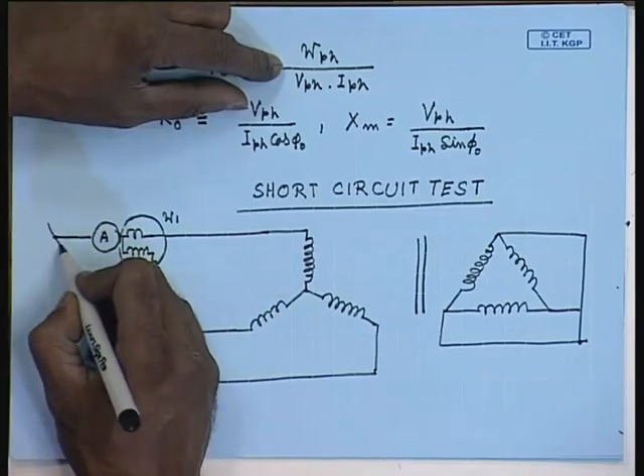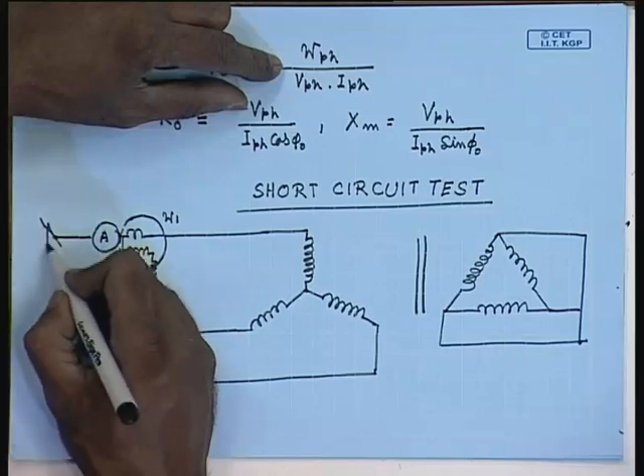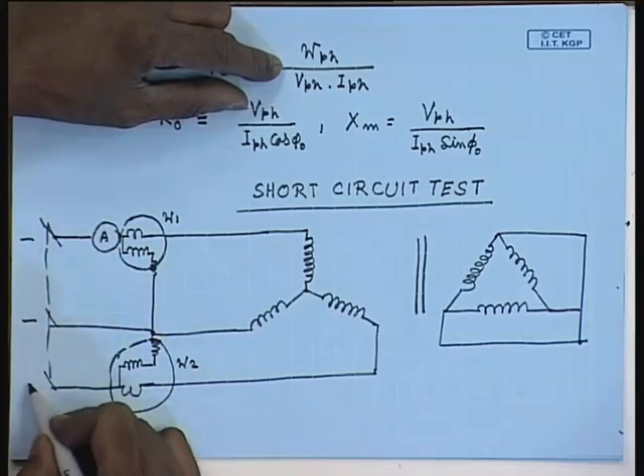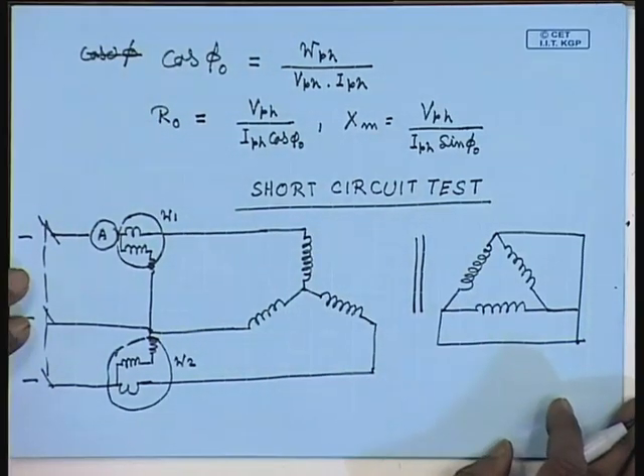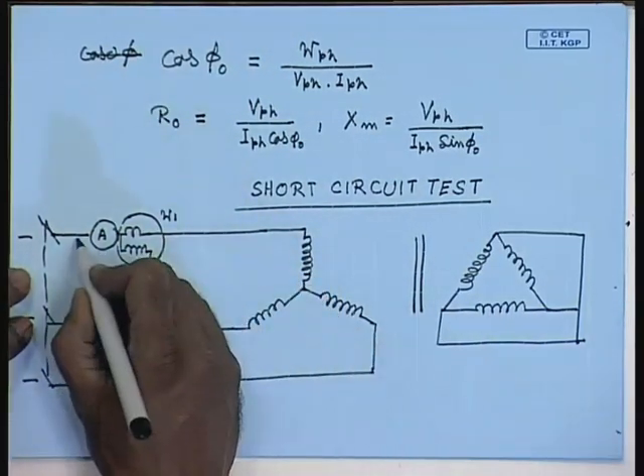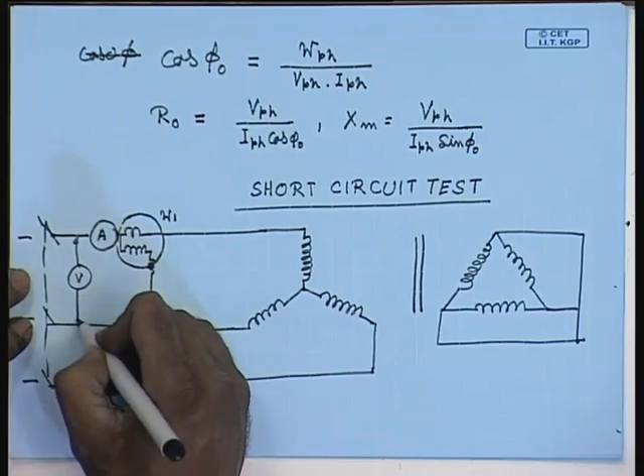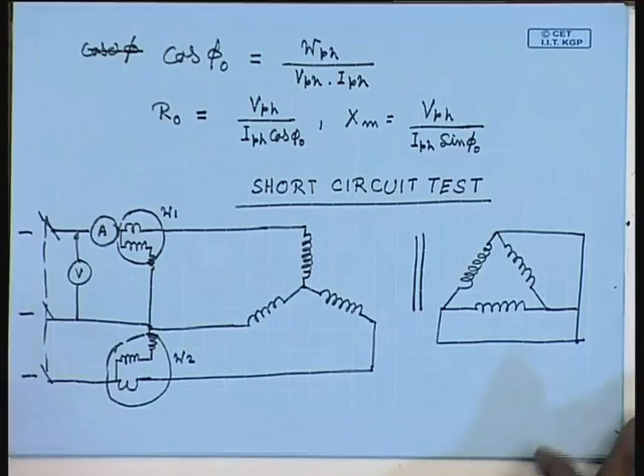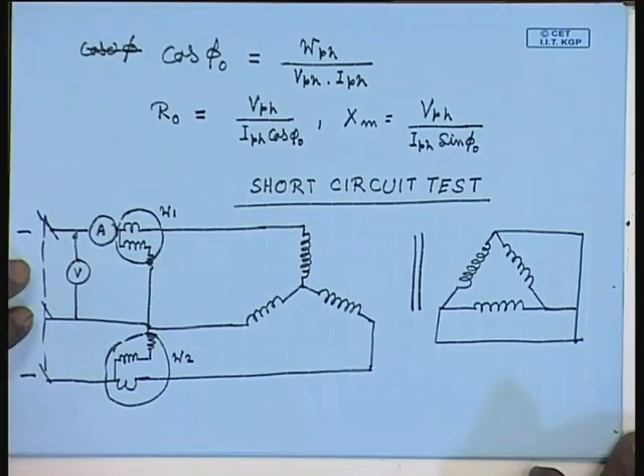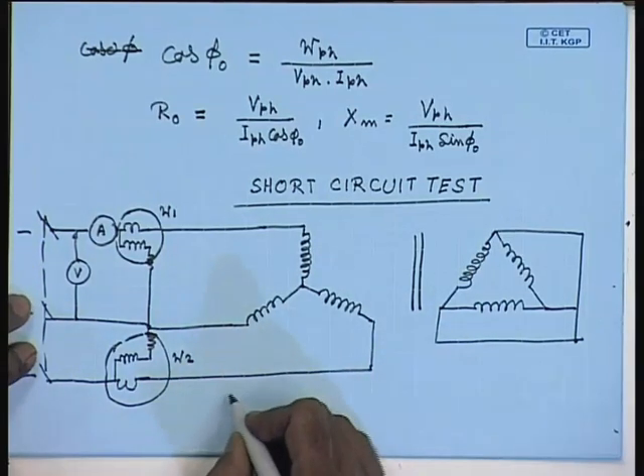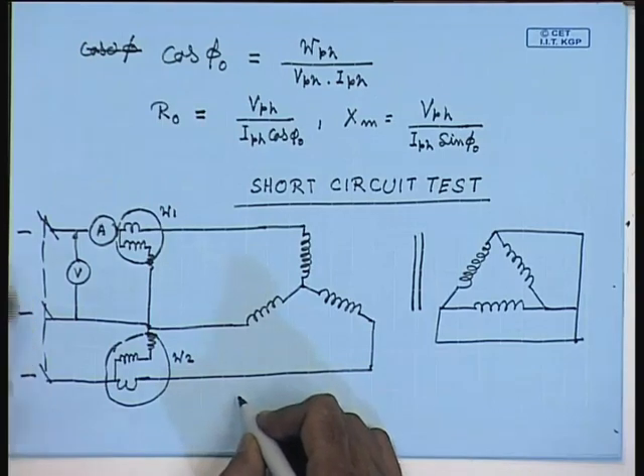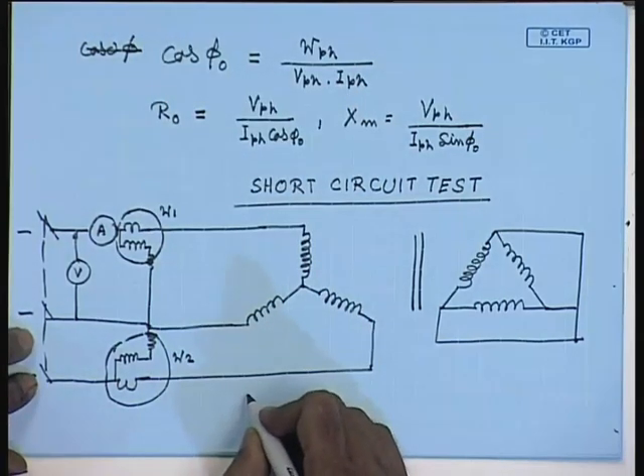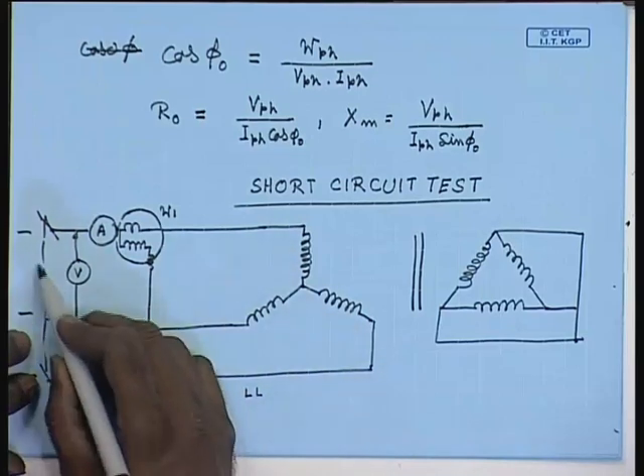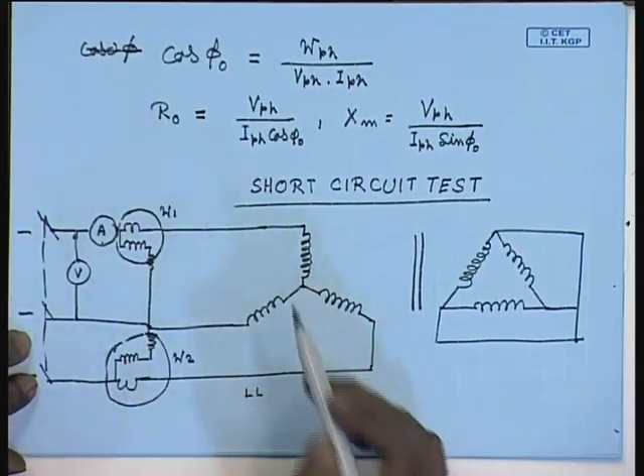This will be supplied from what we call a 3-phase variac in order to control the current flowing into the line. Here again, a voltmeter will measure the line to line voltage. Here again, the readings that will be taken are line to line voltage.